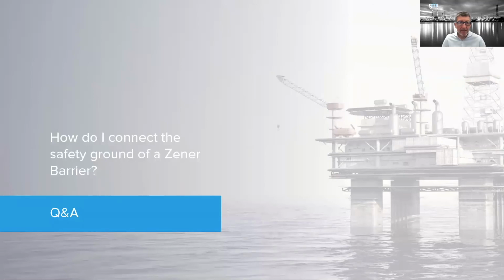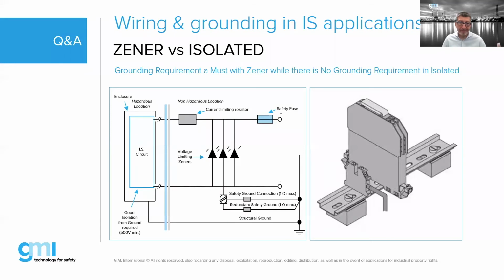How do I connect the safety ground of a Zener barrier? Well, you discussed this already, Bob. Yeah, that picture on the right-hand side. To understand that a little better, a lot of Zener barriers will actually be grounded. You can see they'll typically have earth lugs or earth tabs to make a direct connection. But a lot of Zener barriers are designed to be mounted directly to a metallic DIN rail. And that DIN rail could be attached to a grounding terminal, which in turn is attached to the DIN rail, and then that's tied off.